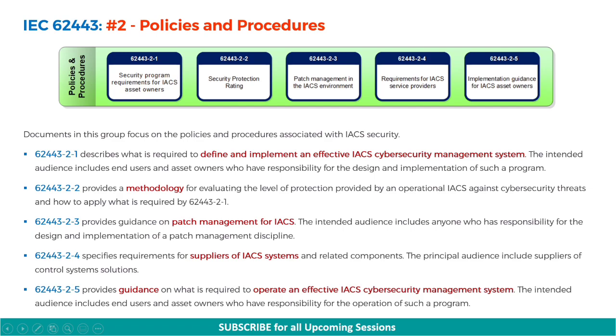62443-2-4 specifies requirements for suppliers of IACS systems and related components, with the principal audience being suppliers of control systems solutions. 62443-2-5 provides guidance on what is required to operate an effective IACS cybersecurity management system, intended for end users and asset owners who have responsibility for the operation of such a program.